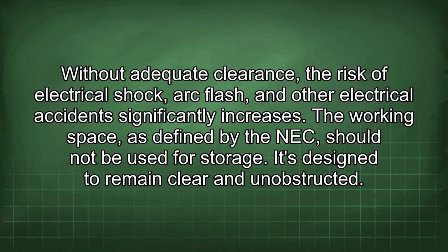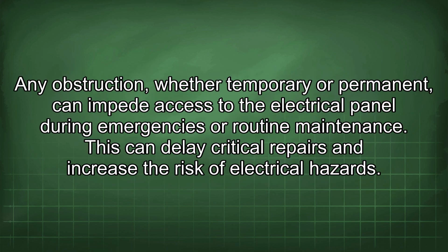The working space, as defined by the NEC, should not be used for storage. It's designed to remain clear and unobstructed. Any obstruction, whether temporary or permanent, can impede access to the electrical panel during emergencies or routine maintenance. This can delay critical repairs and increase the risk of electrical hazards.